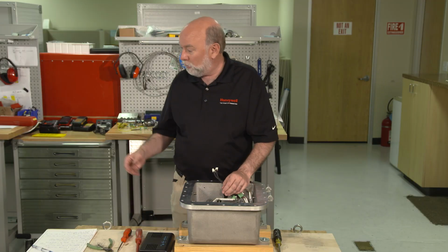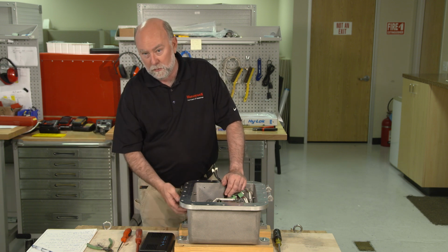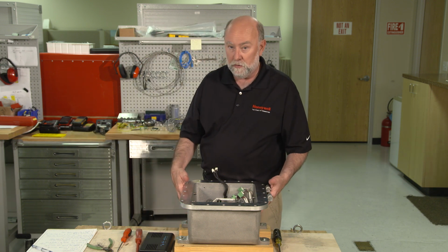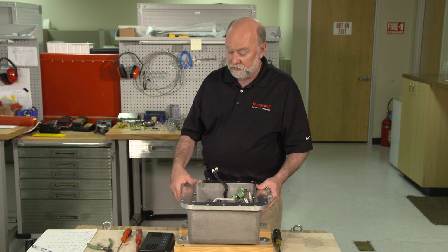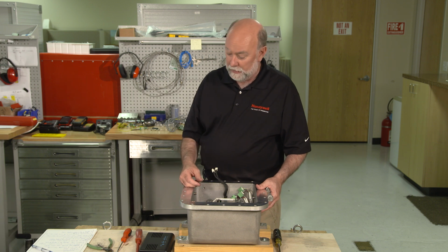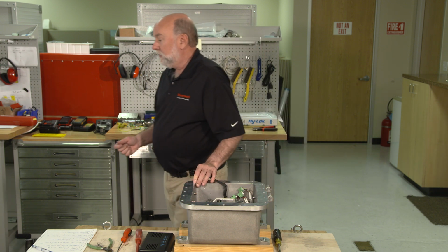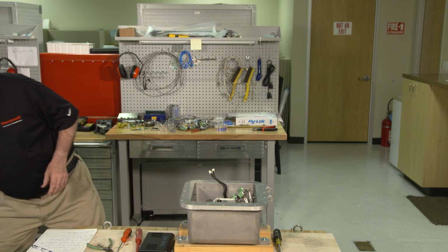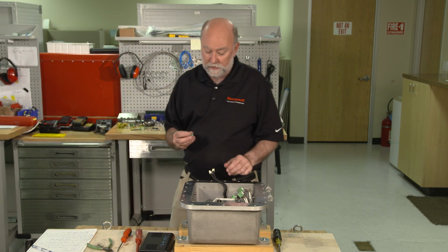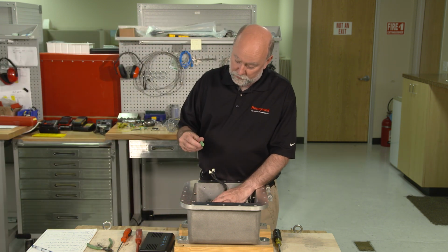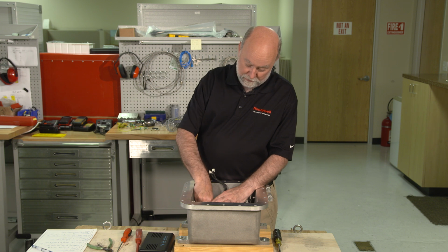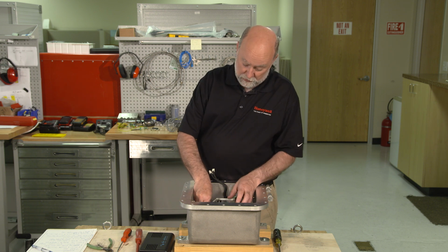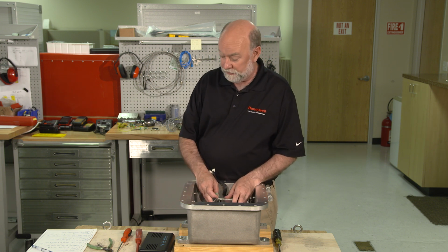At this point, I'm ready to bring my transducer cables back through the cable glands on the side of the box, on your field wired box. Once I bring the transducer cable through each gland, I can terminate those cables into a 3-pin Phoenix connector from the new kit and connect the 3-pin Phoenix connectors to the transducer adapter boards on the left and right sides of the card cage inside here.